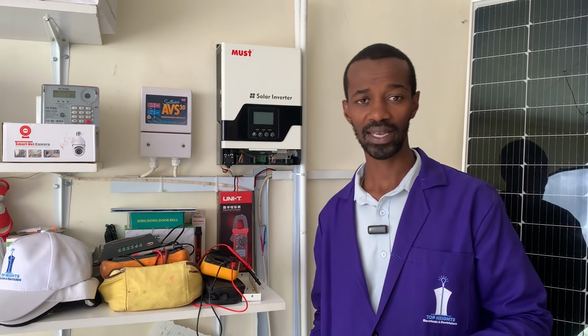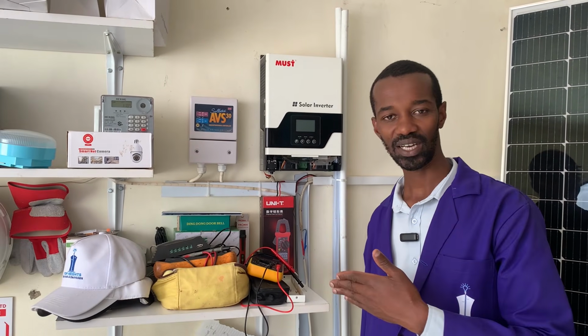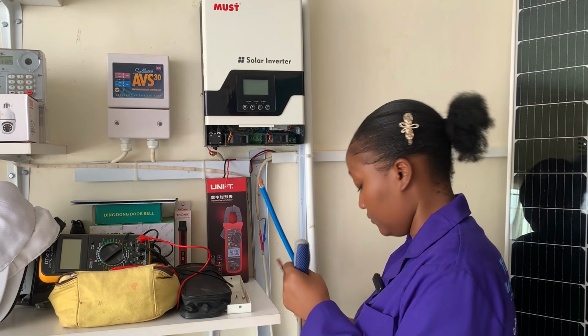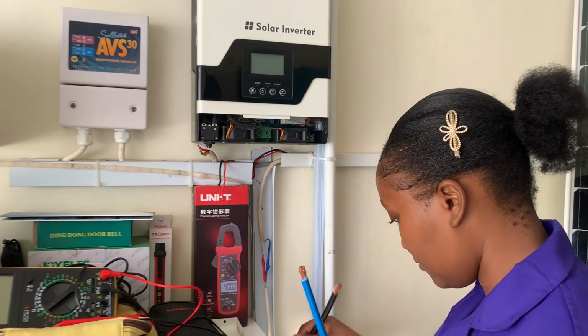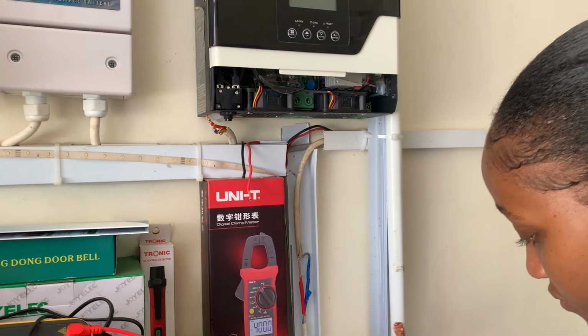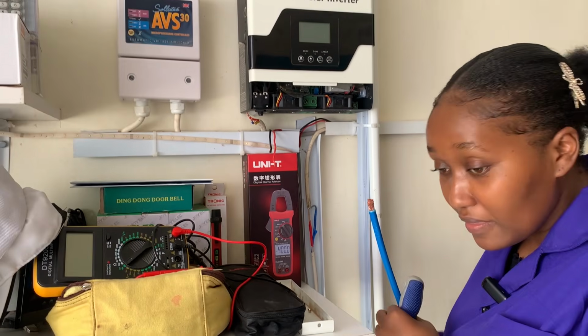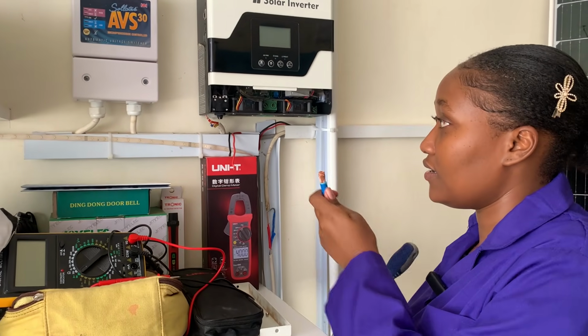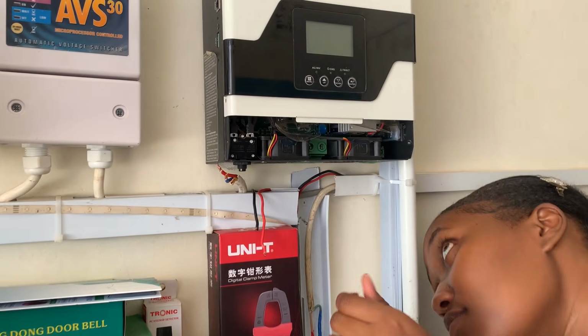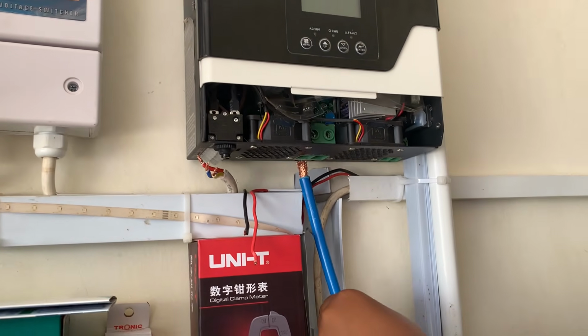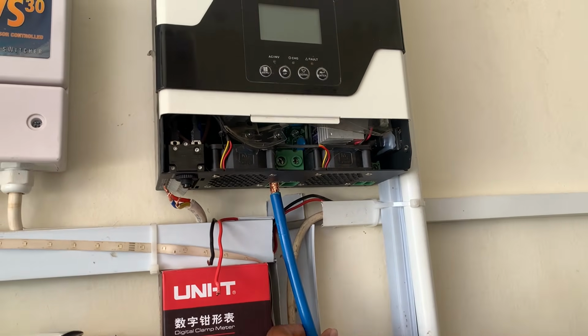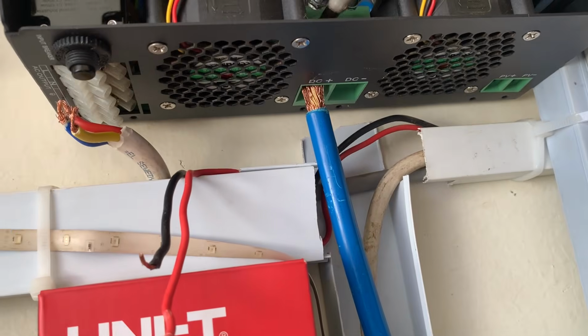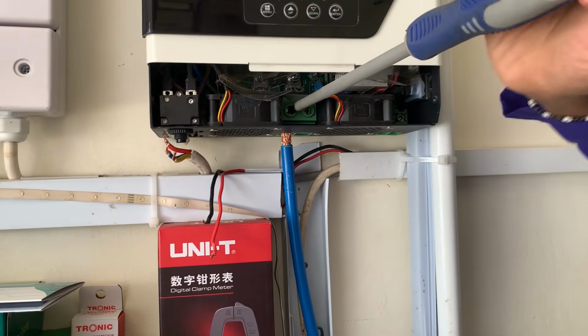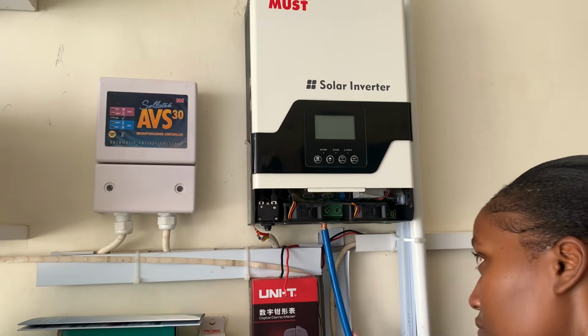Now let's go ahead and reconnect the inverter, starting with connecting the battery. When connecting the system, like we said, you start with the batteries, ensuring that you don't interchange the polarity. What we have actually done is to first start connecting the cables at the inverter, so that in case you slide and the cables come in contact, the battery is not short-circuited.